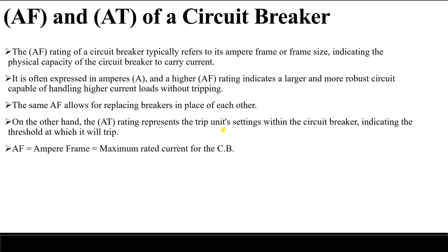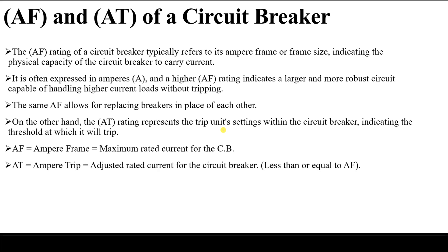So to summarize: AF, or ampere frame, is the maximum rated current for the circuit breaker. AT, or ampere trip, represents the value at which we select our circuit breaker to cut off. And of course, ampere trip is always less than the ampere frame.